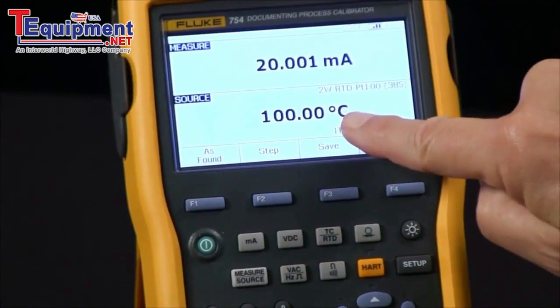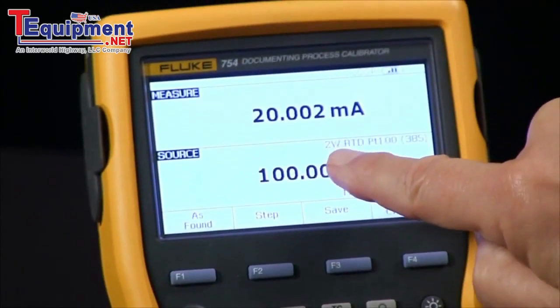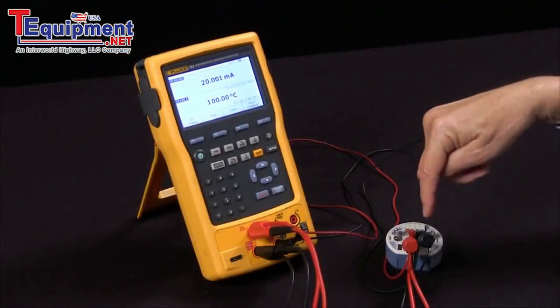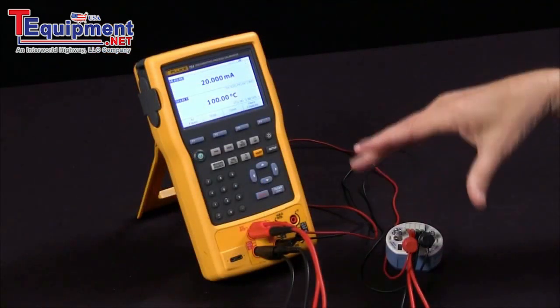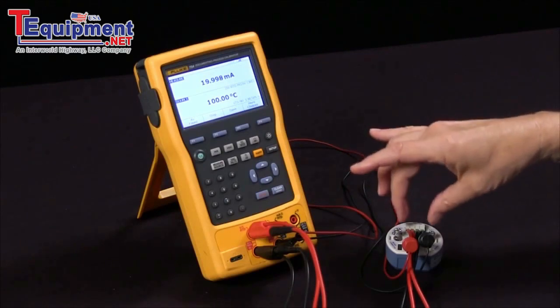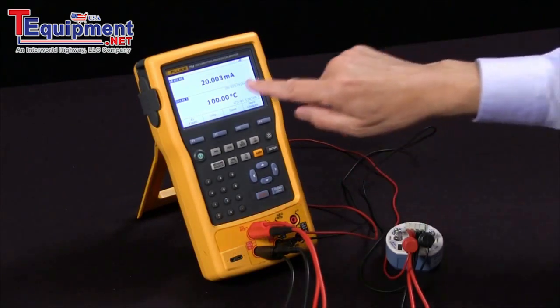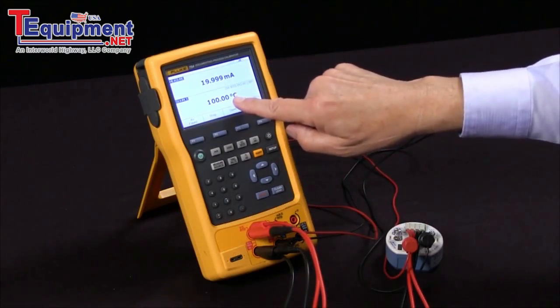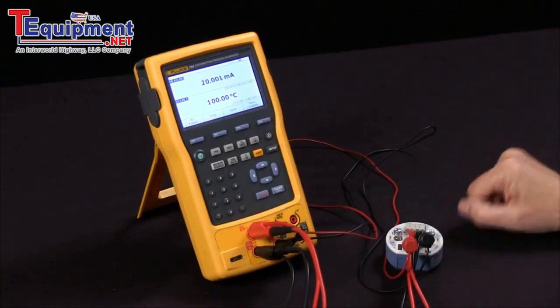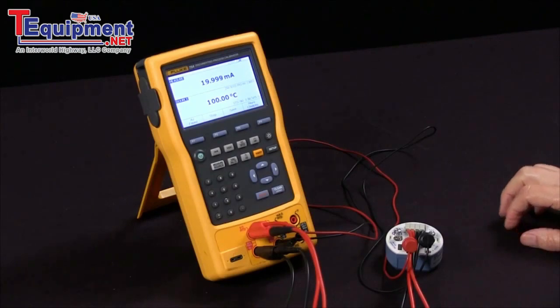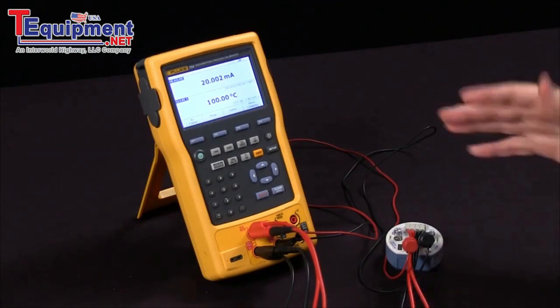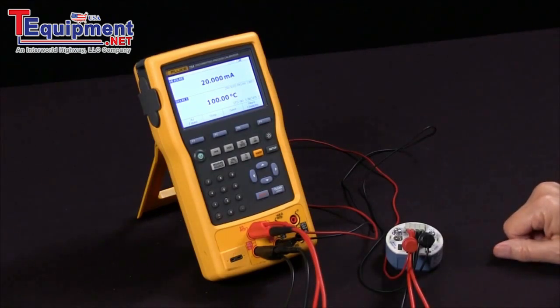Going back to the source measure screen, now I'm sourcing 2-terminal RTD platinum 100 ohm 385 to the transmitter, so I'm simulating a very accurate RTD to the transmitter and it's reading 100 degrees C as it should be. That's how we source an RTD to a device that we're trying to simulate RTD for.